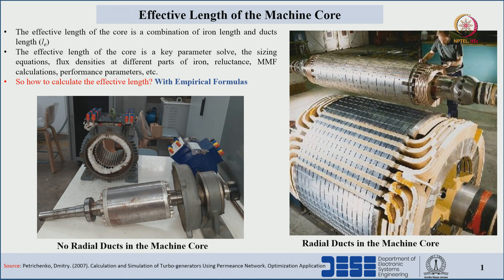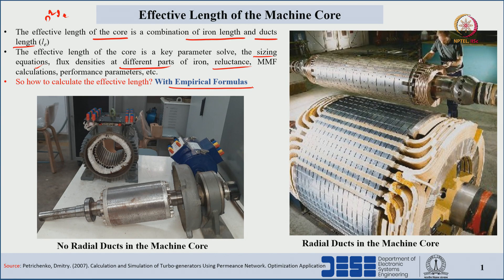The effective length of a core, LE, is a combination of iron length plus the duct length. The effective length of the core is a key parameter to solve the sizing equations where the D²·LE term we have discussed, as well as flux densities at different parts of iron, reluctances, MMFs, and other performance parameters. There are no straightforward equations — some empirical formulas depending on the literature and experience from manufacturers will be discussed in this lecture.